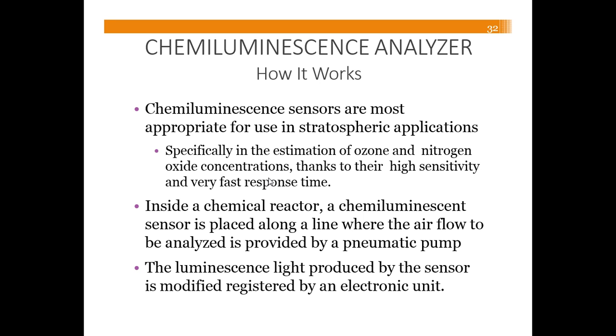How does the analyzer work? The chemiluminescent sensors are most appropriate for use in stratospheric applications, those higher levels of the atmosphere. It's specifically in the estimation of ozone and nitrogen oxide concentrations.